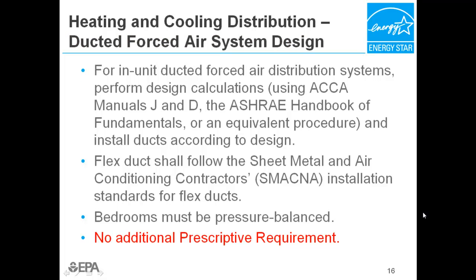Identical to the performance path, in-unit ducted forced air distribution systems must be properly designed and installed, and all flex duct shall follow SMACNA's installation standards. Also, bedrooms must be pressure balanced using any combination of transfer grills, jump ducts, dedicated returns, or properly undercut doors. These are the same prerequisites in both paths.